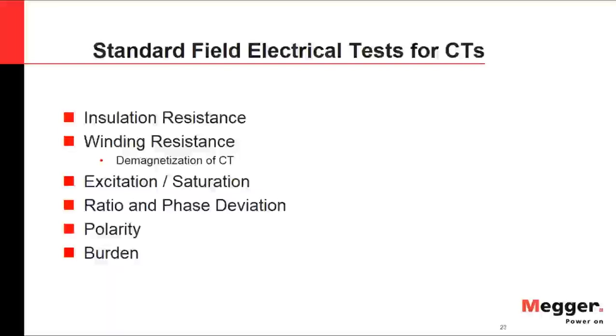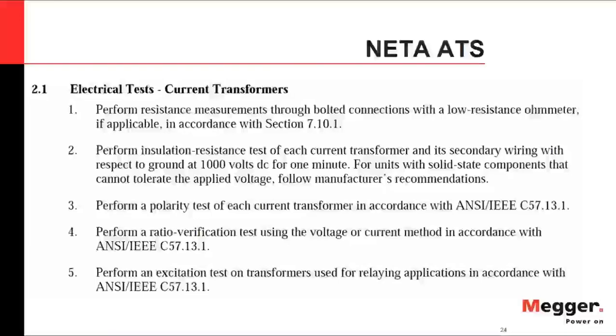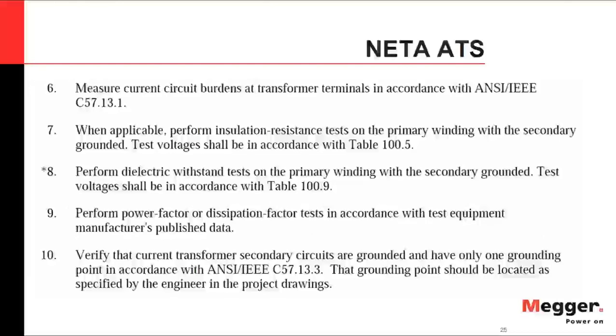Looking at the NETA standard, it requests: resistance or contact resistance measurements, insulation resistance testing not exceeding 1000 volts, polarity test, ratio verification test, excitation test, measurement of the current circuit burden at the transformer terminals, insulation resistance test on the primary winding with secondary grounded, and if possible, power factor or dissipation factor test. It also requires verifying that transformer secondary circuits are grounded according to the standard.